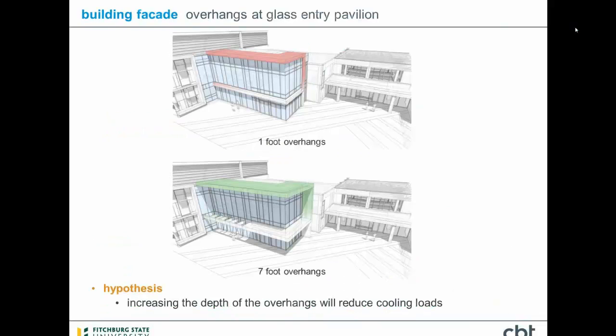In addition to some of the overall building analysis, where we were looking at components throughout the building, we looked at some key elements and spaces around the building. Shown here is an entry pavilion into the building, which is on the quad side. It was intended to be a focal point for the entry of the building. It's also a major two-story space, a gathering space within the heart of the building. It also happens to be southeast facing, so we've got 2 stories of southeast facing glass, and the concern was that it was going to be, if not fairly uncomfortable, it would represent a fairly significant cooling load that if we could avoid, we would.